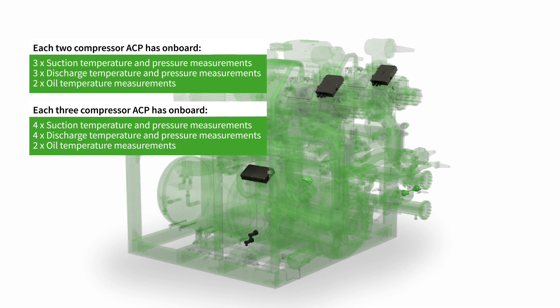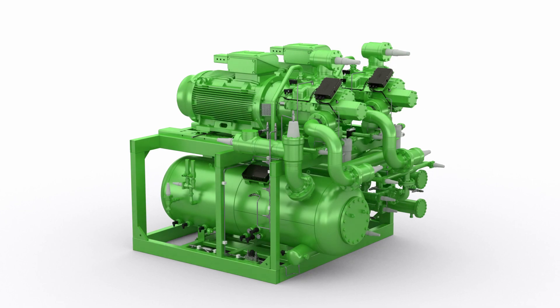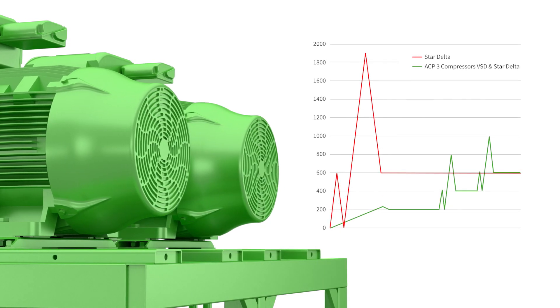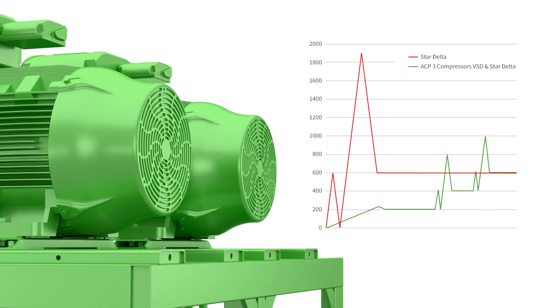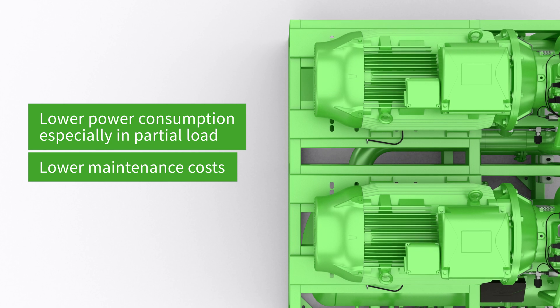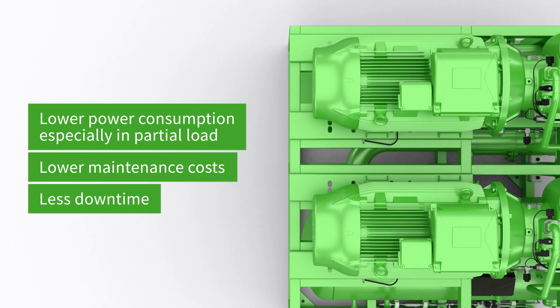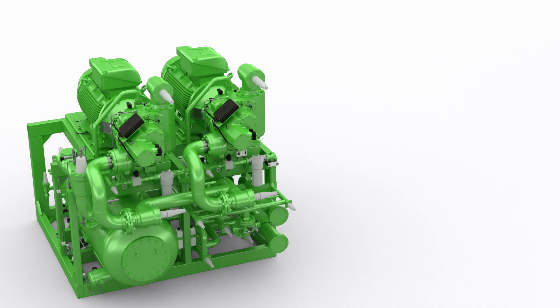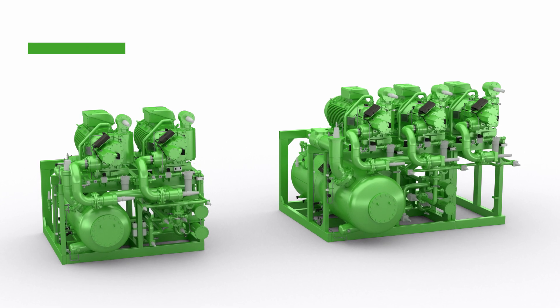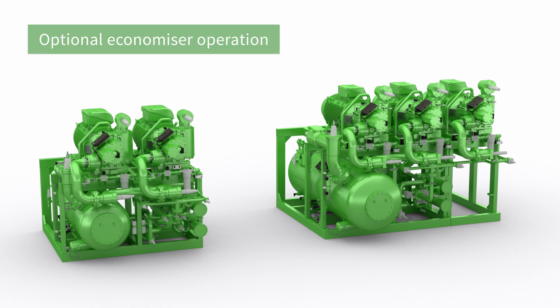The apportioning of the complete capacity over several compressors ensures a significant reduction in the starting current, even without frequency inverter or soft starter option. Overall, lifecycle costs are significantly reduced in comparison to systems with just a single compressor. Bitzer Ammonia Compressor Packs are available with two or three compressors as well as in a booster version, and the ACP can be optionally equipped with an economizer.